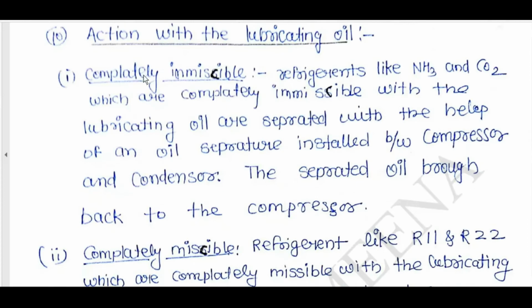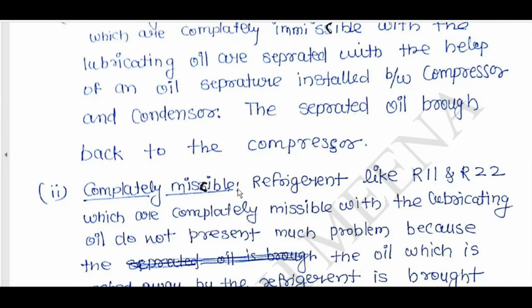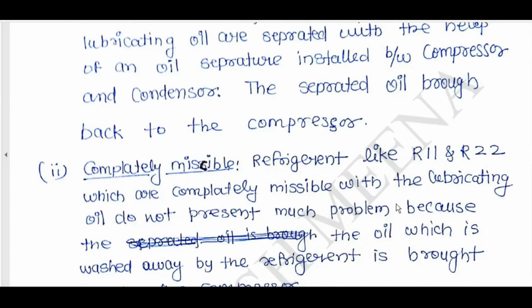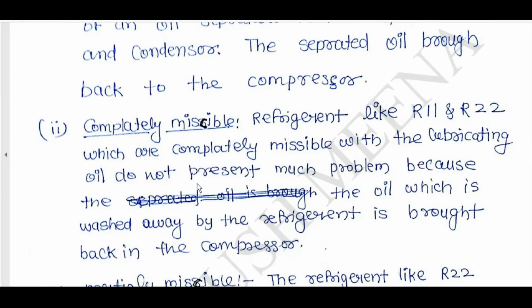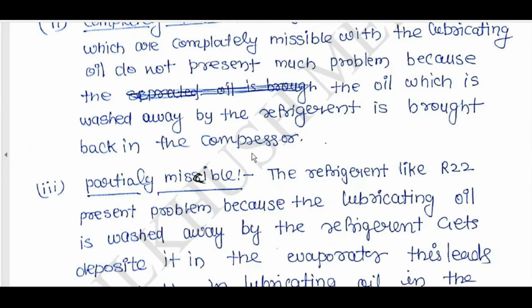Action with lubricating oil: completely immiscible. Refrigerants like NH3 and CO2, which are completely immiscible with the lubricating oil, are separated with the help of an oil separator installed between compressor and condenser. The separated oil is brought back to the compressor. Completely miscible refrigerants like R11 and R22 do not present much problem, because the oil which is washed away by the refrigerant is brought back to the compressor.